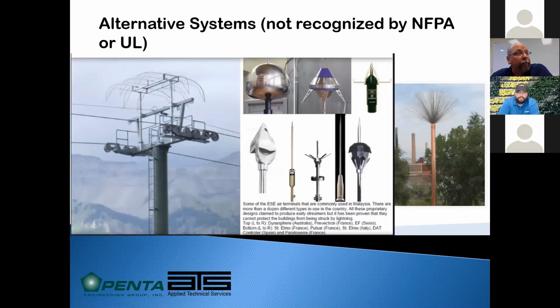Yes. NFPA and UL recommend, some are a little bit open, they say periodic, it depends on the area. NFPA actually does recommend annual inspections. It also should be inspected anytime any mechanical equipment is added. We see window washers many times damage the lightning protection as they're going over the edge of the buildings if they're using rope access. So the recommendation is an annual inspection. If you have a UL master label, UL, another third-party firm, will come out after a system is installed if it is applied for a master label, do a third-party inspection, then issue the master label, and that is good for 5 years before it has to be recertified.